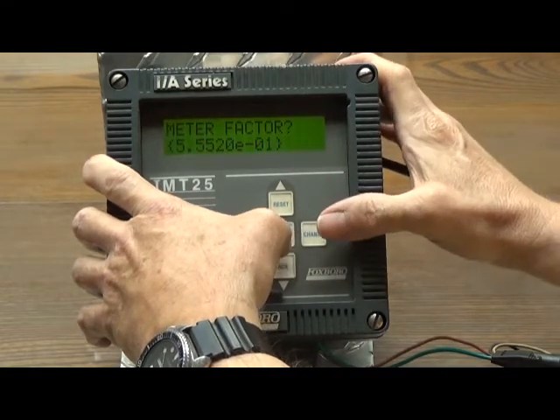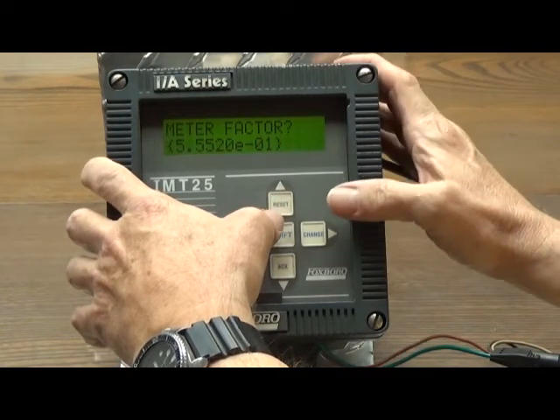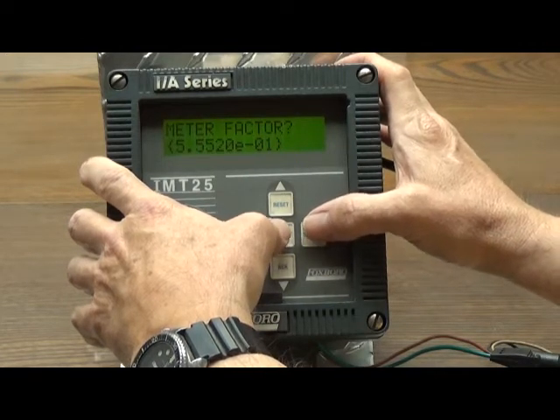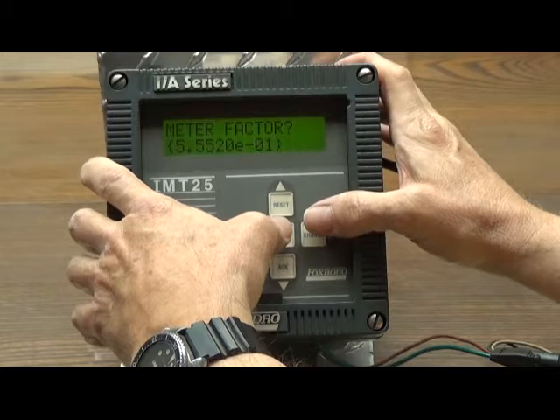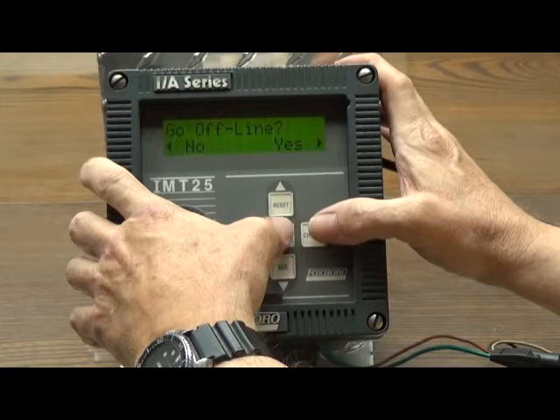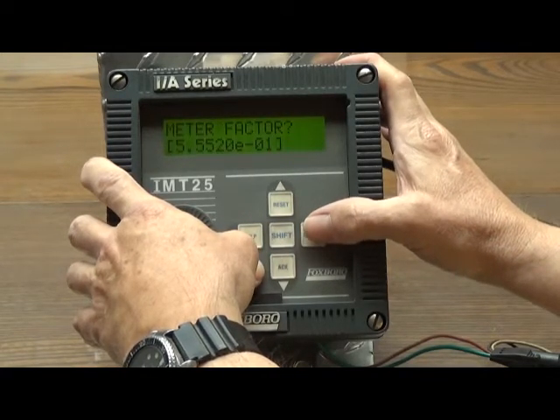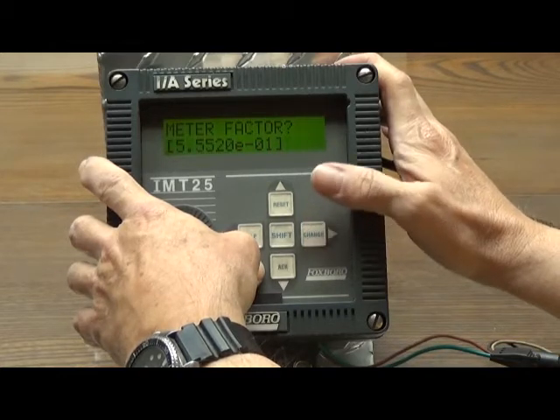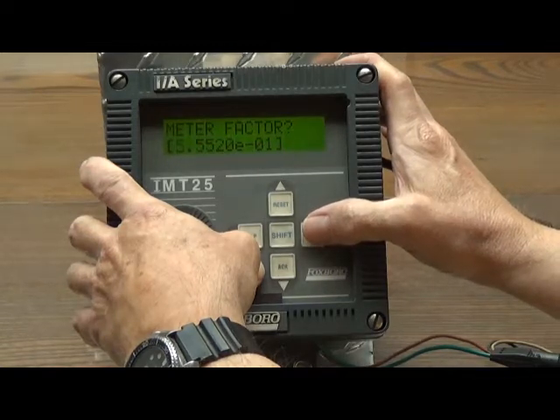The change or right arrow key to get to the meter factor itself — it displays the current setting. We're going to be changing this to a meter factor of .5731, but you'll notice that it's entered in exponential format. We're going to have to make sure that we retain the e-01 at the end of the number. To proceed, we hit shift change and it'll ask us to go offline, and we answer yes. Then we have the calibration factor displayed inside square brackets. Use the change button to advance through the calibration factor to get to the digit that needs to be changed, and then make up or down arrow changes to change the digit.